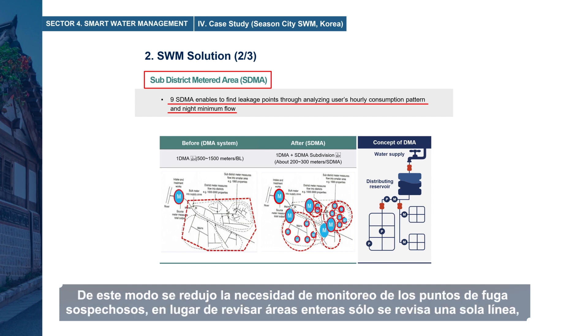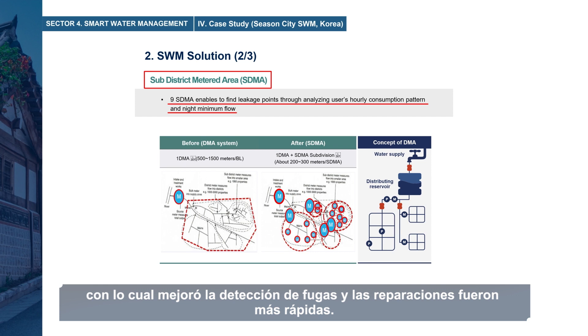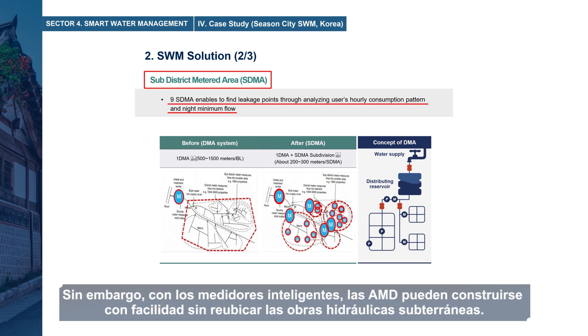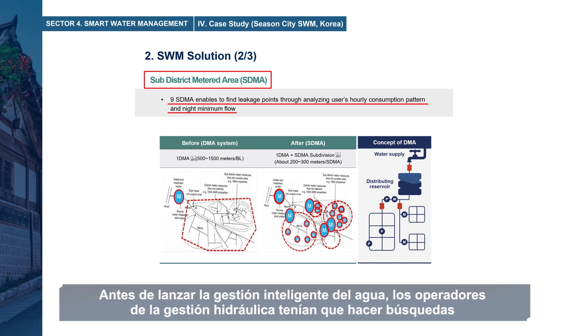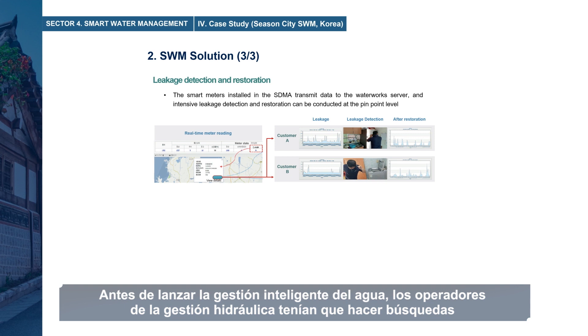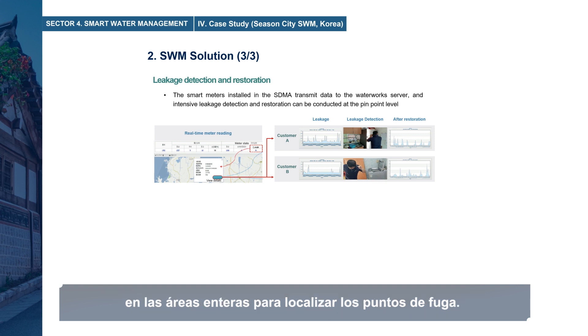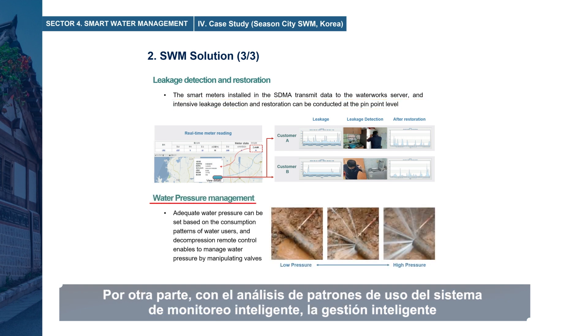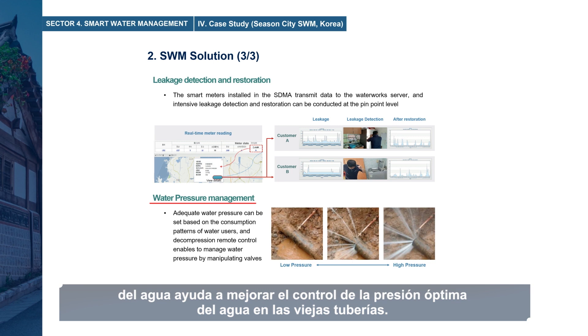This narrowed down the need to monitor suspected leakage points from entire areas to a single line, thereby improving leakage detection and enabling faster repairs. Traditionally, DMAs are made by physical construction of waterworks grids. However, with smart meters, DMAs can be easily built without relocation of underground waterworks. Before launching smart water management, operators had to search whole areas to locate leakage points. However, the system showed accurate leakage points effectively with less effort and time. Through use pattern analysis of the smart monitoring system, smart water management also helps improve optimal water pressure management in aged pipes.